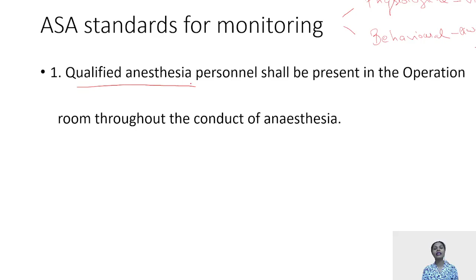For that, it is mandatory that the oxygen concentration in the inspired gas as well as the blood levels of oxygen has to be calculated, which could be done with the help of first oxygen analyzers, which can tell you about the oxygen concentration in the inspired gas, and they do have an alarm. For example, the minimal oxygen which is required when the patient is undergoing controlled ventilation is 33%. So if the oxygen concentration decreases below 33%, within 5 seconds an audible alarm sets in, which can never be muted.